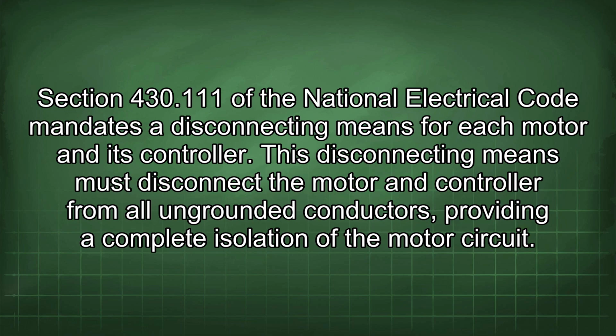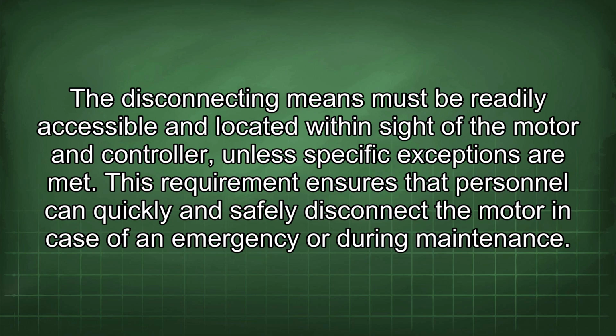Section 430.111 of the National Electrical Code mandates a disconnecting means for each motor and its controller. This disconnecting means must disconnect the motor and controller from all ungrounded conductors, providing a complete isolation of the motor circuit. The disconnecting means must be readily accessible and located within sight of the motor and controller, unless specific exceptions are met.